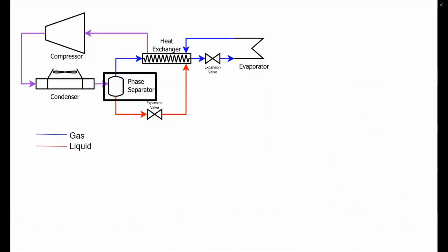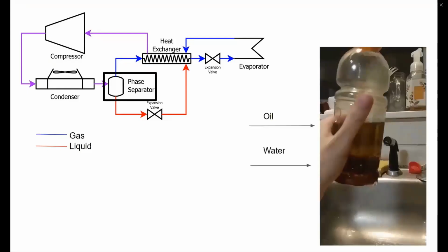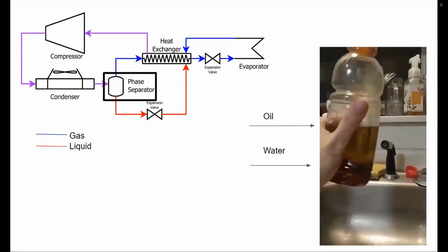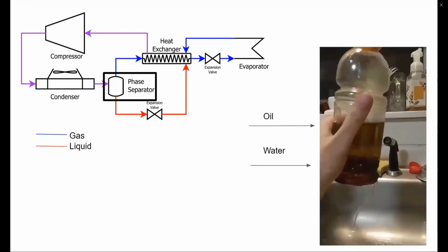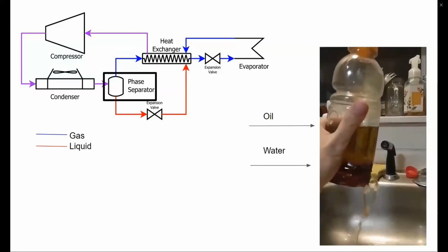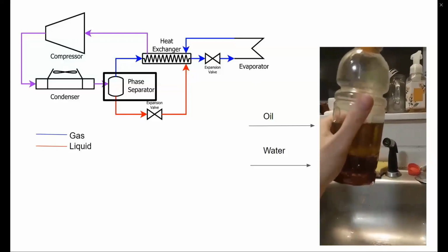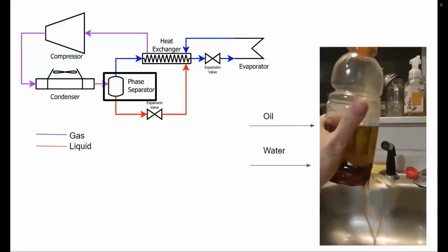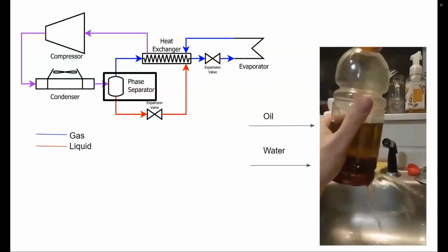On the market today, one of the main ways in which ultra-low temperature chilling is achieved is through the use of an auto-cascade cycle, which is shown above. This system relies on a delicate and expensive blend of refrigerants that are designed to separate during normal operation. That being said, the system is kind of like a mixture of water and oil, and if a leak develops, the delicate balance of refrigerants can be easily upset. If the mixture does get upset, this entire system must be purged and recharged.